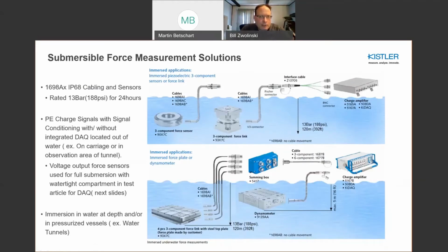So they're in a very dry environment, and you basically get the benefit there of having charge signals coming up to the charge amplifiers and having this infinite rangeability, if you will, with this type of solution. So when you have this solution, you have a lot of flexibility in terms of the signal conditioning solution.